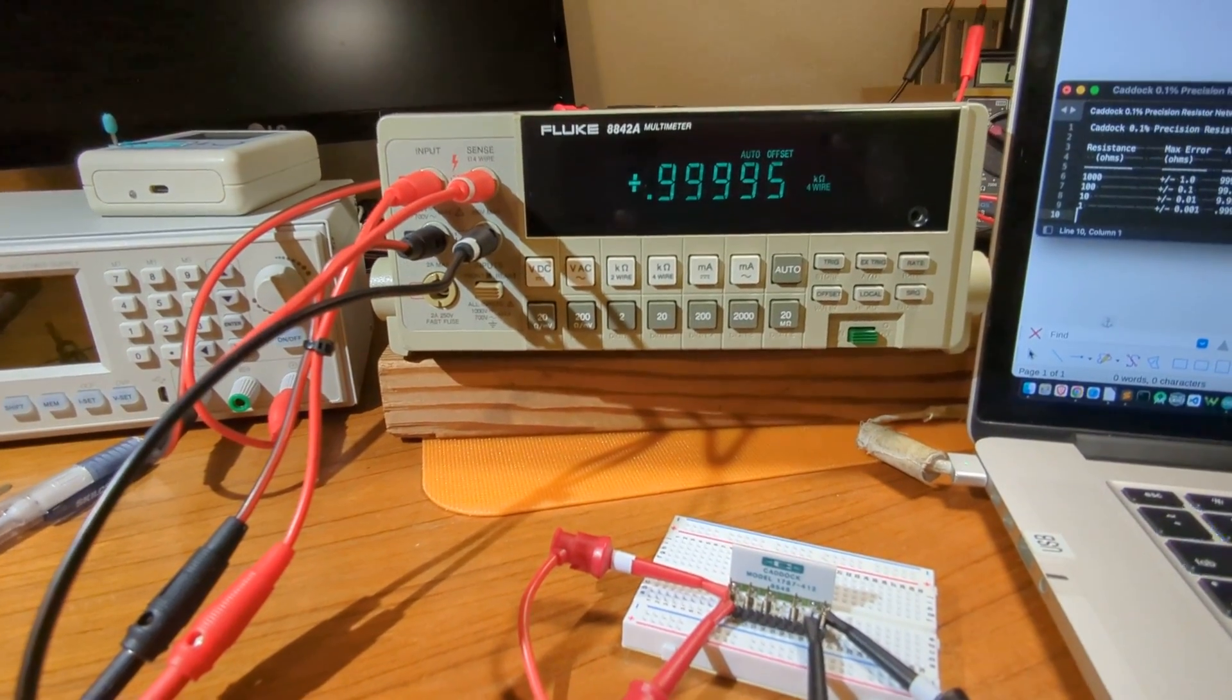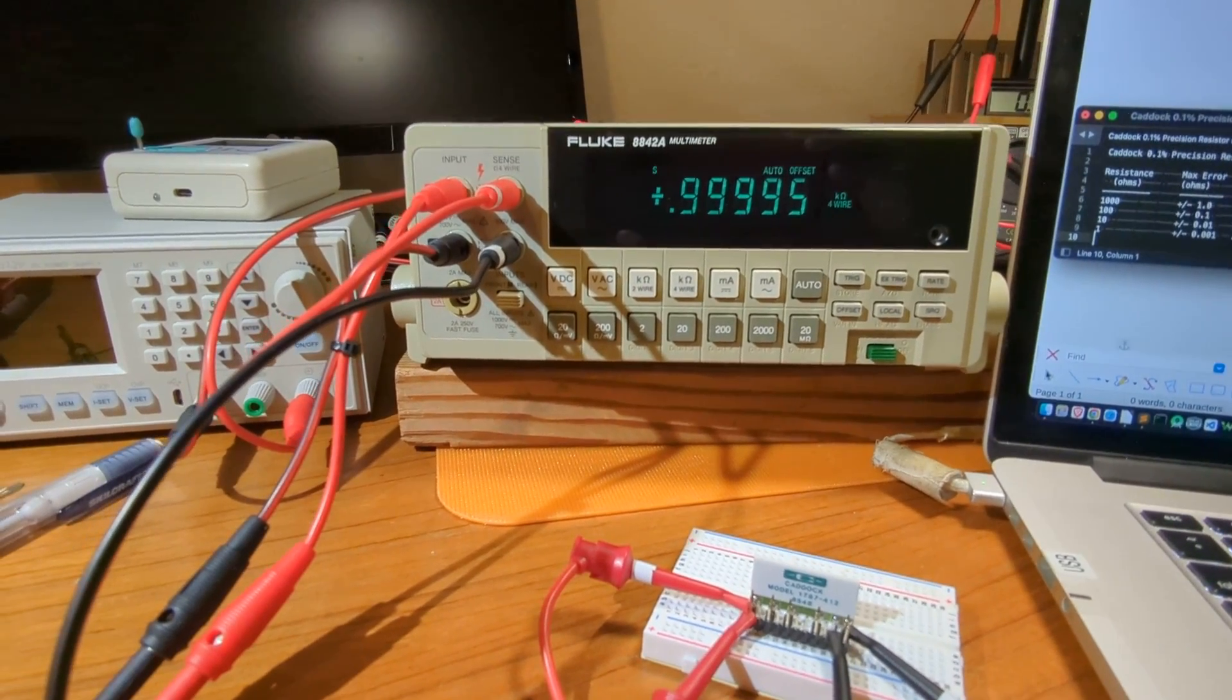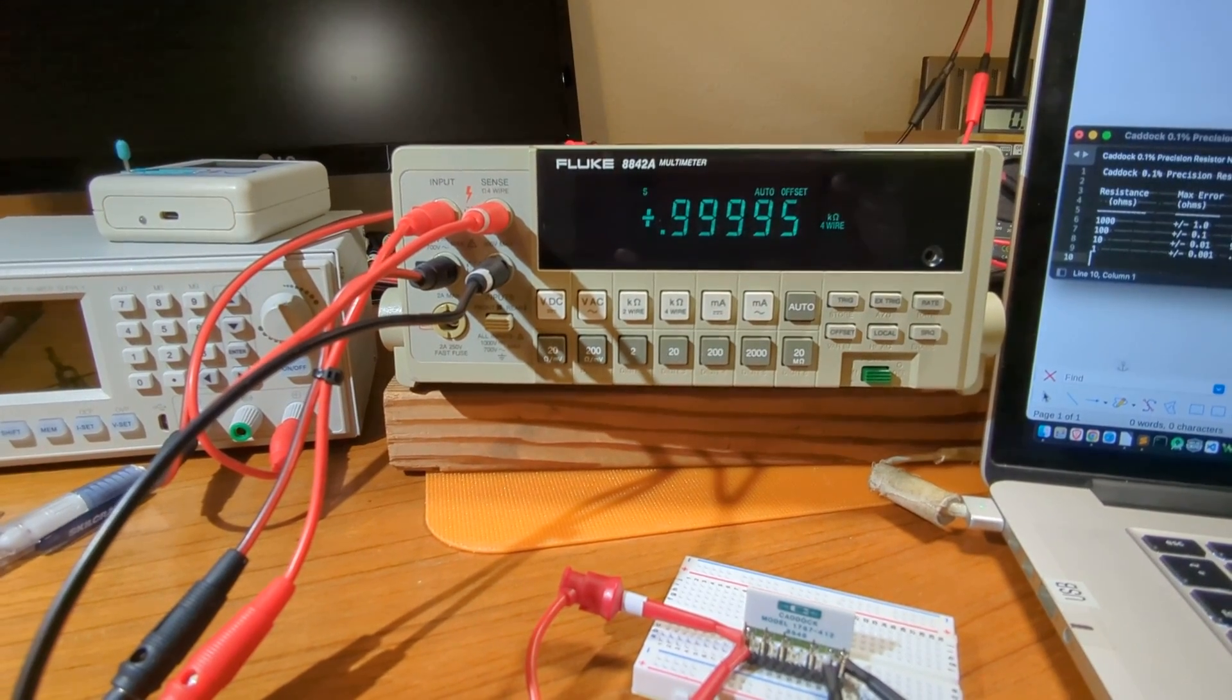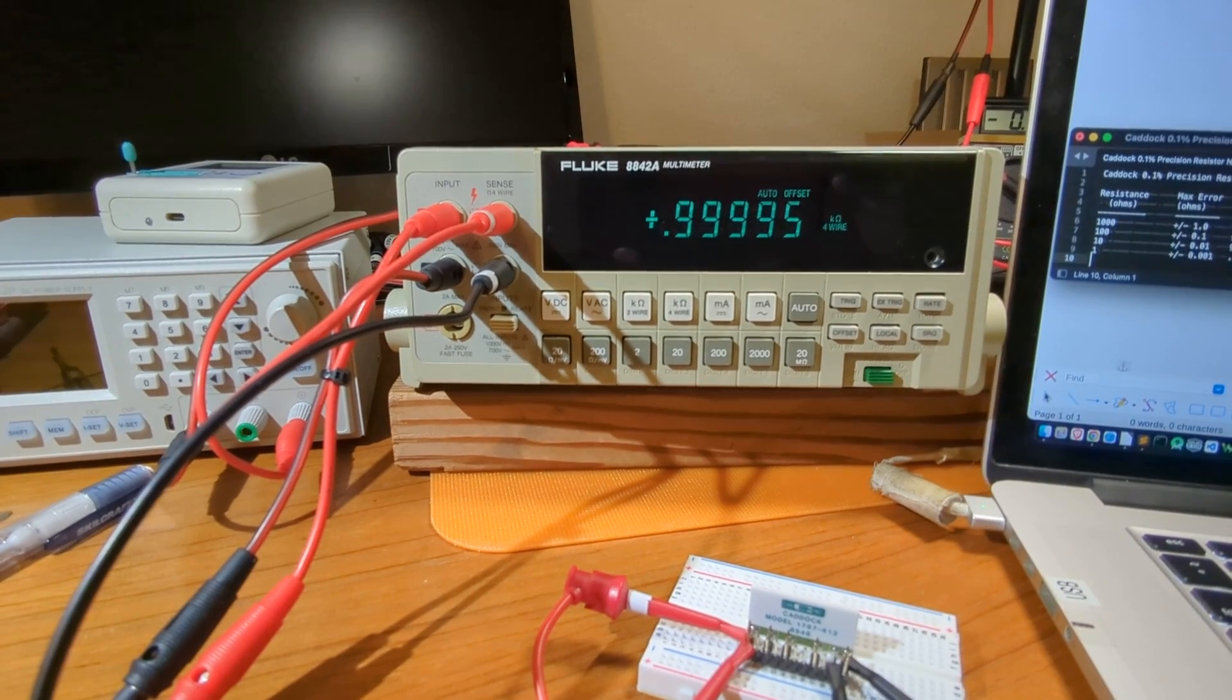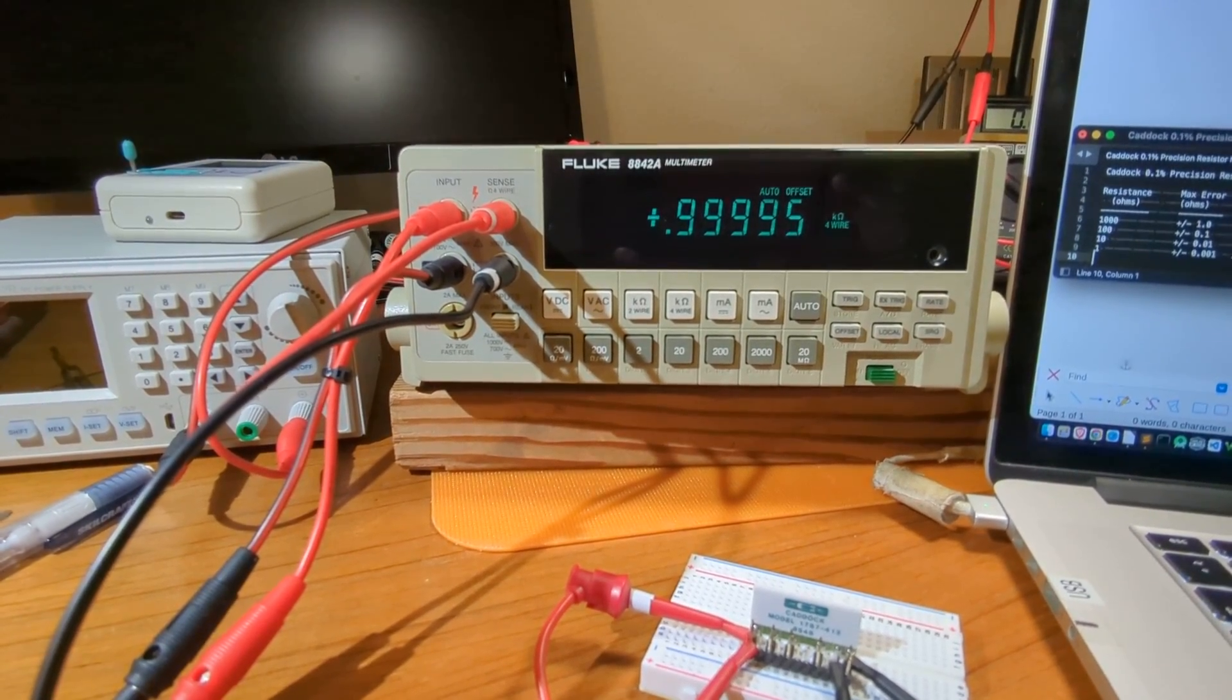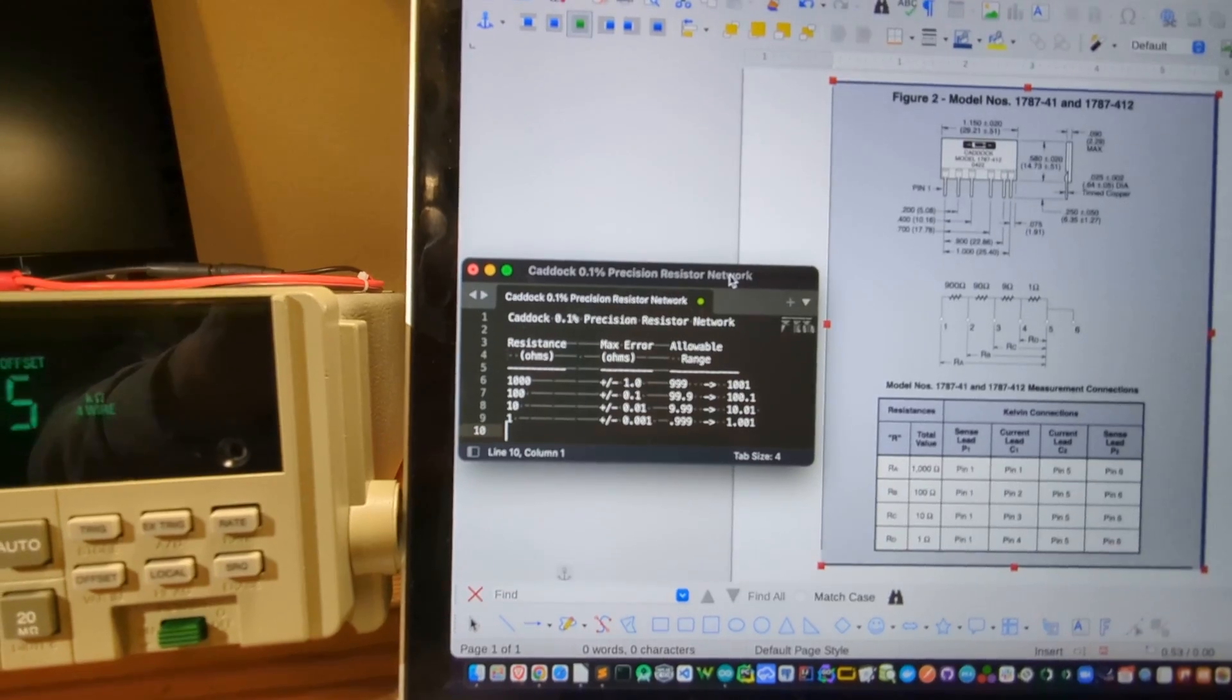I'm currently set up measuring the 1,000 ohm resistor, and we're looking at the value on the Fluke in kiloohms, and it's reading 0.99995 kiloohms, which is 999.95 ohms. And back to that list, you can see that's well within spec.